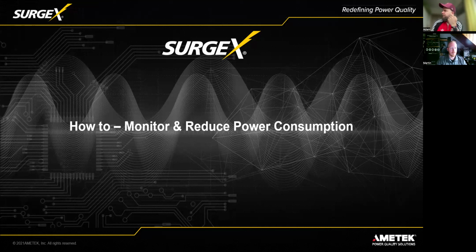Is there a scenario when we should use two 1200 watt UPS units instead of a single one? Yes, when you want to split up the circuitry. For example, one circuit running just the back end, the signal monitoring, the Ethernet switch and the network, and another running just the front end. So it's possible to split them into two circuitries, and then it's more useful to use two 1200 watt UPSs.